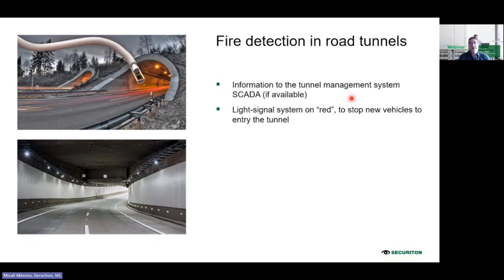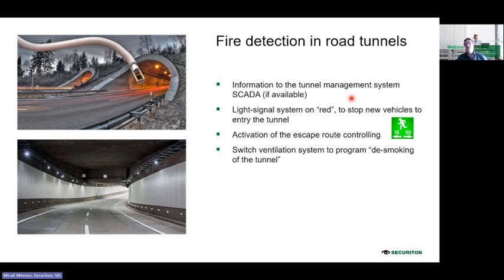fight the fire. Then also very important is the activation of the escape route, all the lighting that you have to trigger so that the people inside the tunnel can easily find the way out and protect themselves. And of course, the ventilation system has to be programmed for de-smoking, and therefore it's very important to bring out all the smoke for the fire brigade.